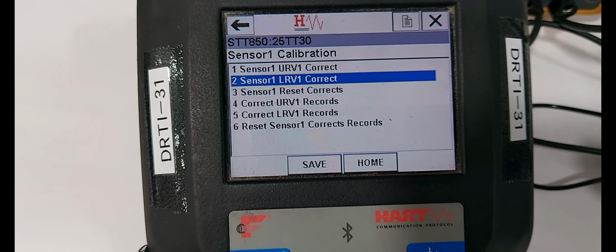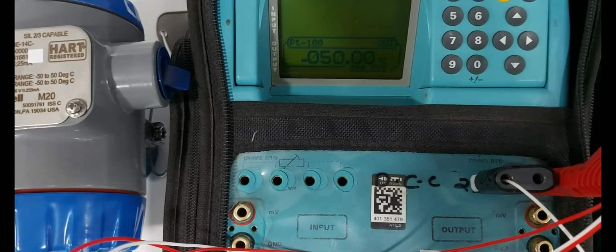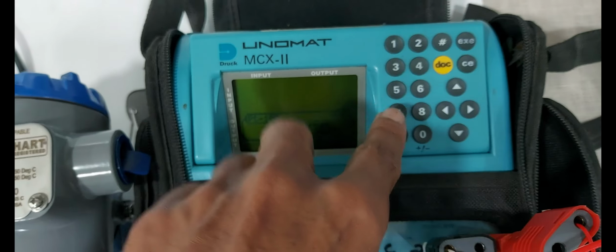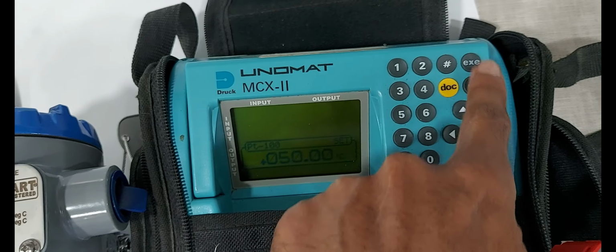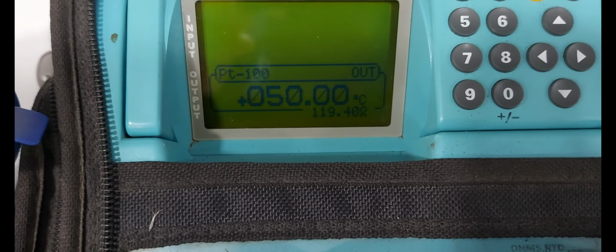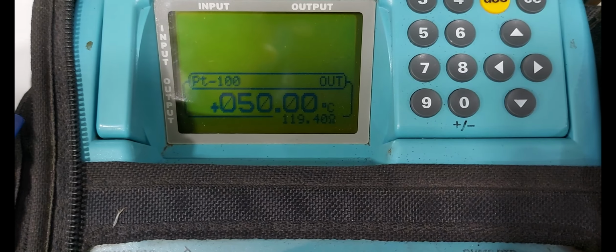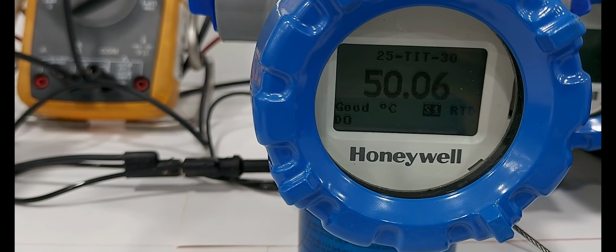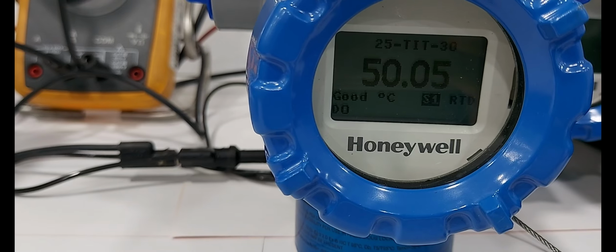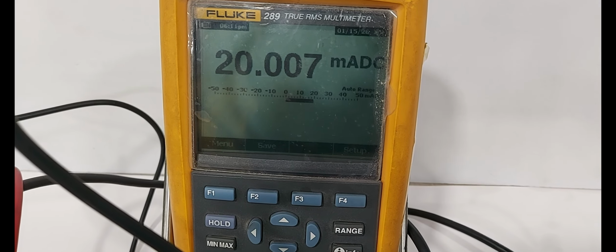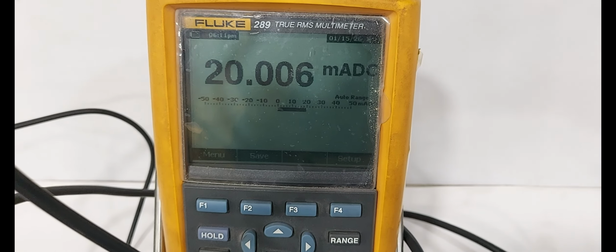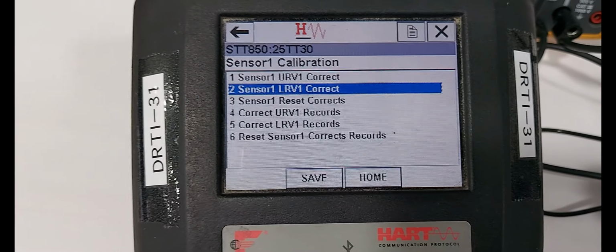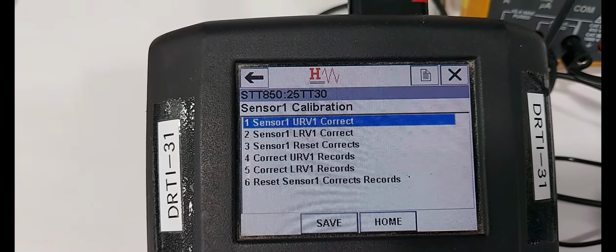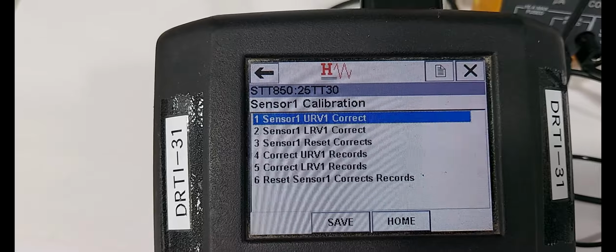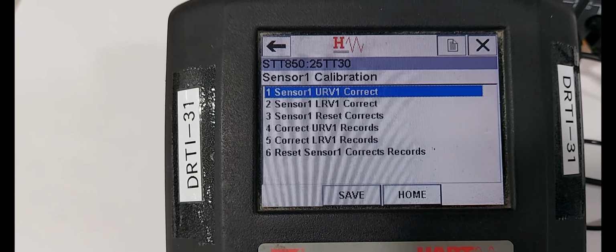Next we are doing the upper sensor trim. First enter the value 50 degrees, enter. Now the corresponding resistance is 119.40 ohms. The transmitter display is showing an error, 50.05 degrees. The reference multimeter is also showing the error, 20.006 milliamps DC. Next we are removing the error. Select the sensor 1 URV calibration. Select 1, then OK.